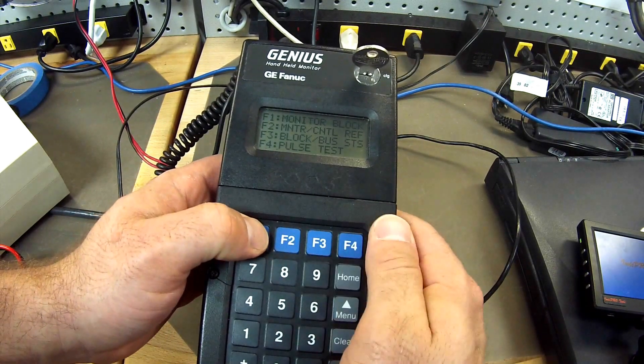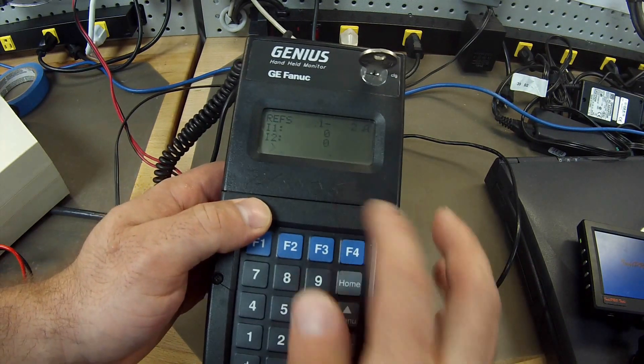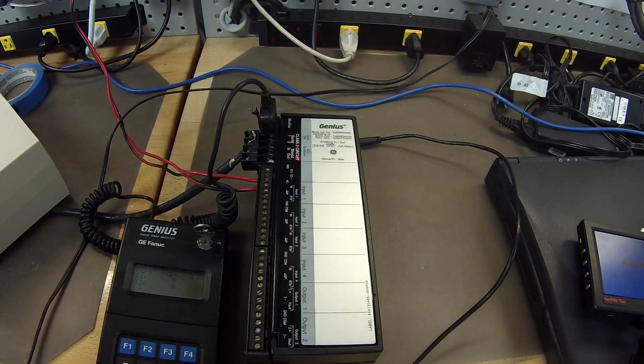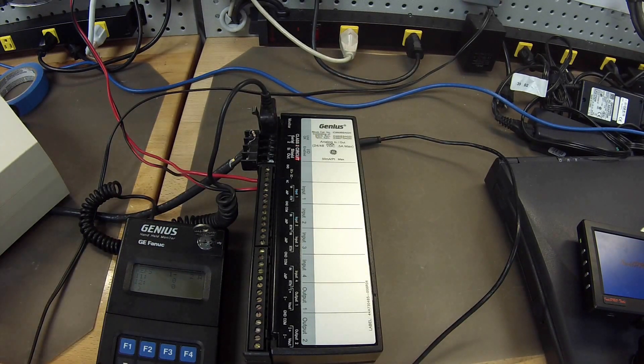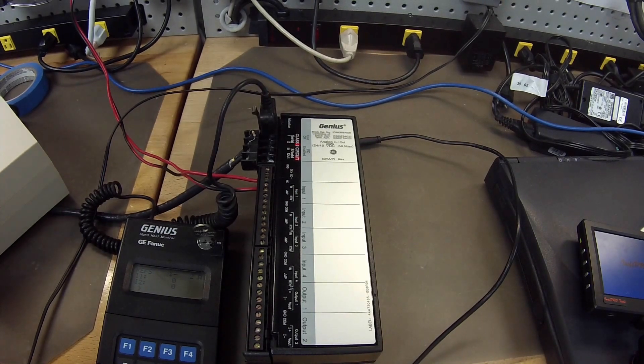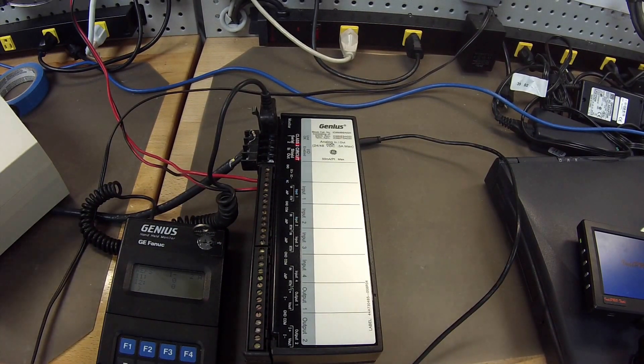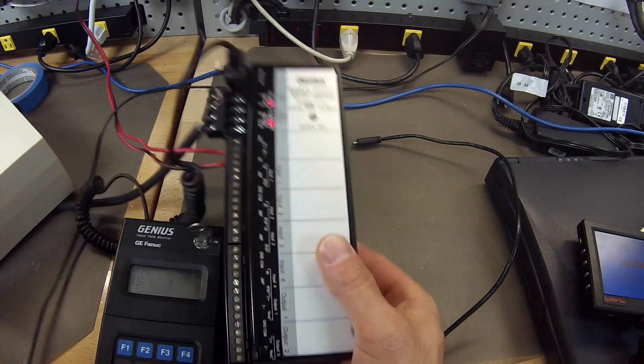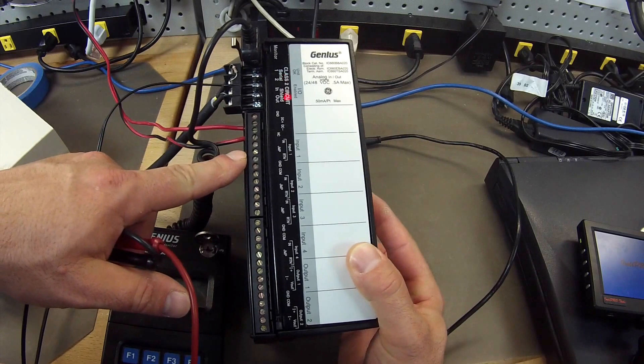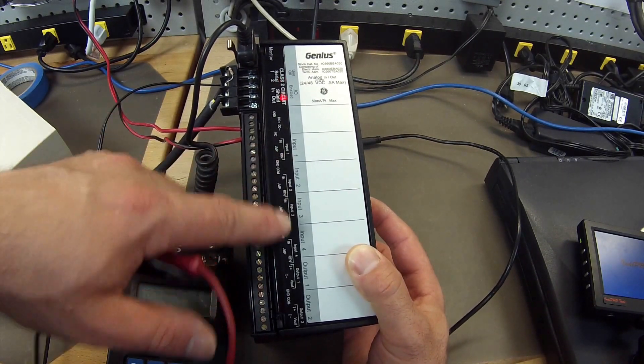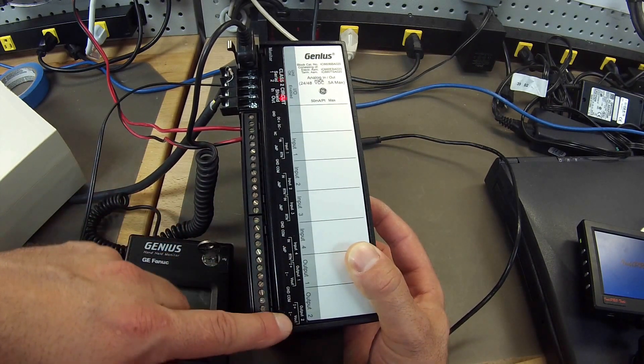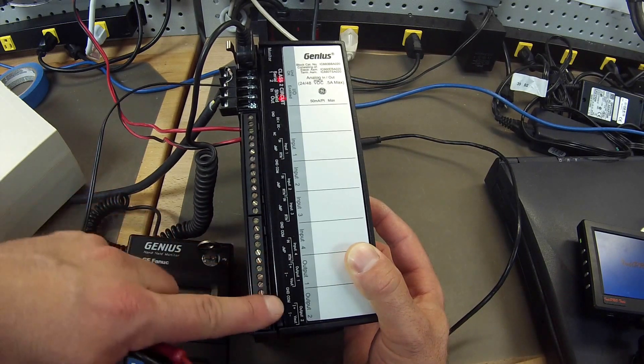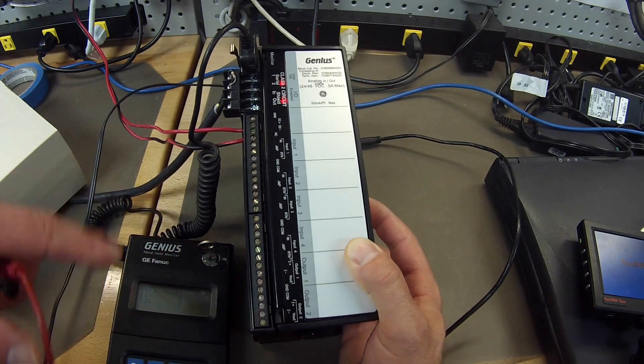F2, F1 monitor block. Now I have a 4 to 20 milliamp generator. So this generates a very small milliamp value. I have two probes that I am going to use to connect to my inputs. I am going to be using the same inputs and outputs of course as I was using for voltage. They connect through the same area. For the inputs, input and return 1, 2, 3 and 4. And then when we get to the outputs, it is a little bit different. We are going to be touching I plus and I minus and I plus and I minus to the corresponding outputs.